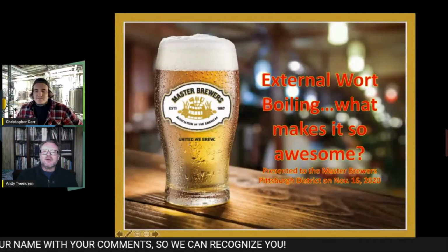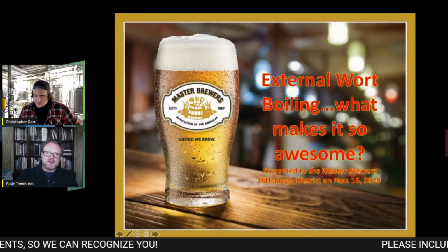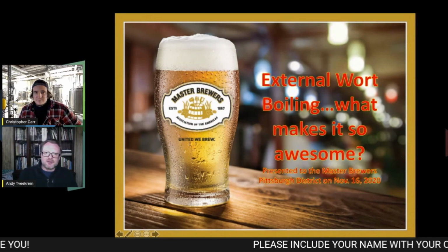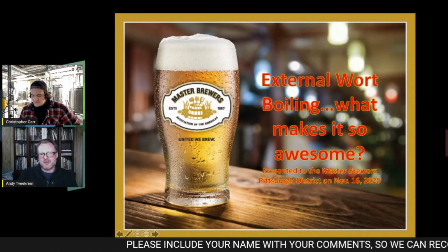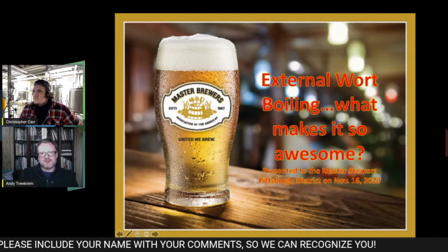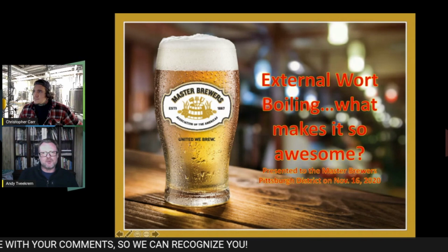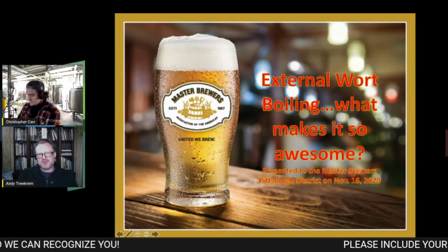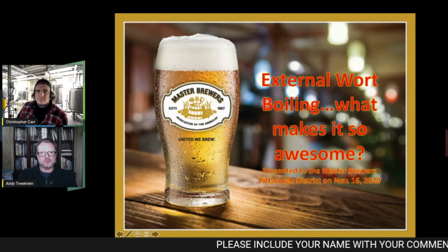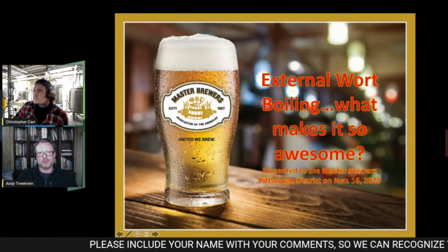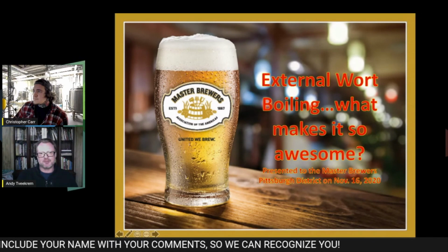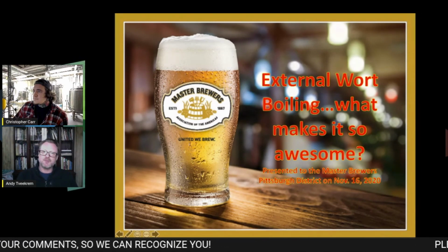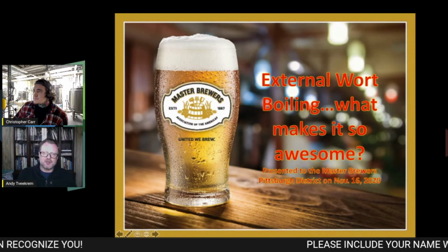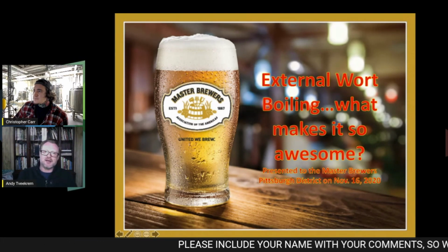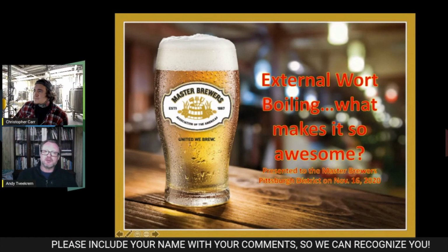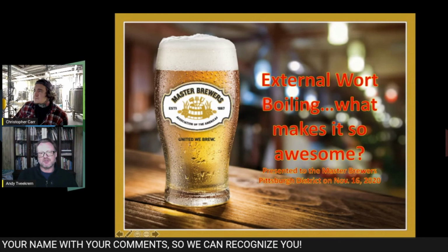So what I wanted to talk about is external wort boilers, because I think there's a lot of people using, on a small scale, just steam jacketed kettles or direct fired kettles, and that's all well and good. But once you get up to, I'd say, 20 to 25 barrel size, then you start wanting better control over your kettle boil, so a few options open up. Traditionally, a lot of people put in an internal calandria, with tubes and heating coils inside the kettle, and they work. But I think there's a better, more elegant solution, which is the external wort boiler.